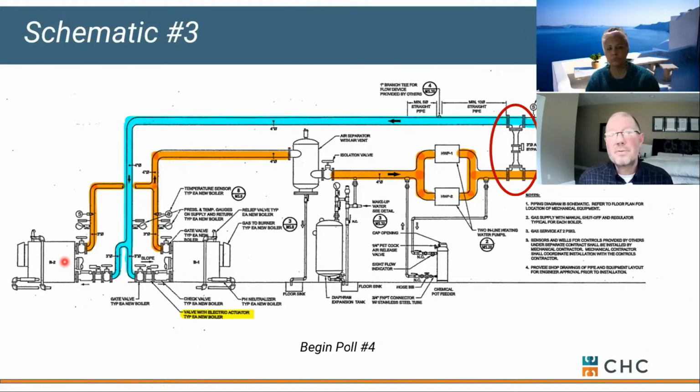So to your point, if you've got boilers closely spaced on a skid in a mechanical room, and you're off by a foot or two, is that the end of the world? I'm going to tell you no. I'm with you on your point. Your delta T might be a little bit different between boiler 1 and boiler 2, but is it enough to cause a major problem? No. I agree with you. My answer is no.